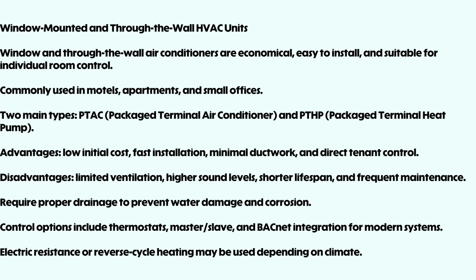Advantages: lowest first cost of any HVAC option, simple plug-in installation and quick service by replacement. Individual room temperature control, no ductwork required. Disadvantages: limited ventilation capability, higher noise levels due to proximity to occupied spaces, shorter lifespan, typically 10 to 15 years. Drainage and condensation management must be handled carefully to prevent water damage.